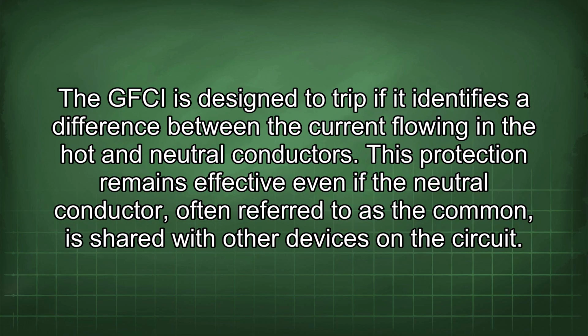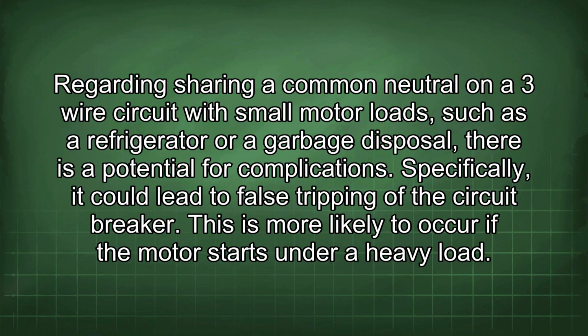The GFCI is designed to trip if it identifies a difference between the current flowing in the hot and neutral conductors. This protection remains effective even if the neutral conductor, often referred to as the common, is shared with other devices on the circuit. Regarding sharing a common neutral on a 3-wire circuit with small motor loads, such as a refrigerator or a garbage disposal, there is a potential for complications. Specifically, it could lead to false tripping of the circuit breaker.